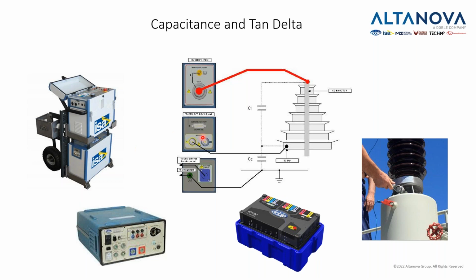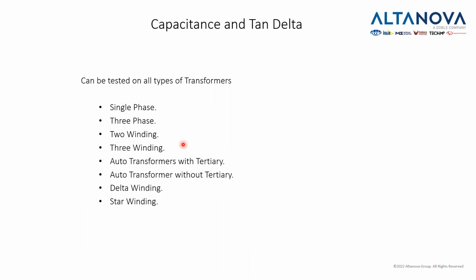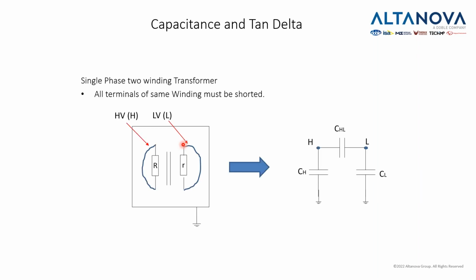One of the ways you can do a test using these test sets is, for example, to do this test on the body of the transformer or the bushings. In this case, we are connecting to the tap adapter and generating high voltage here on the top and measuring the current here and obtaining a value. All types of transformers can be tested with tan delta test: single phase, three-phase, 2 or 3 winding transformers with or without tertiary, auto transformers, transformers with delta or star winding.